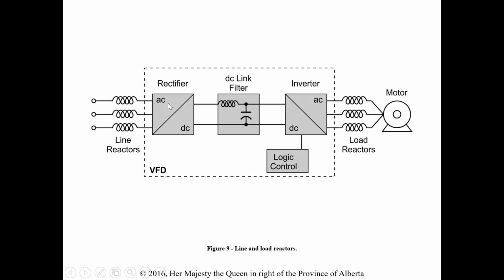What's kind of interesting to see in this first diagram is that this is very similar to our UPS. The only thing we don't have is the DC storage batteries. So we still have a rectifier where we're taking AC down to DC. So now we have DC going into this DC link section, which is filtering and smoothing out our DC to get the most steady state value of DC we can. And then it's going to an inverter and outputting AC back to the motor.